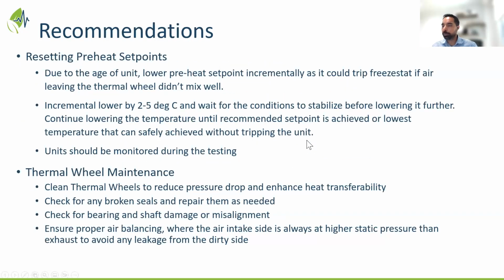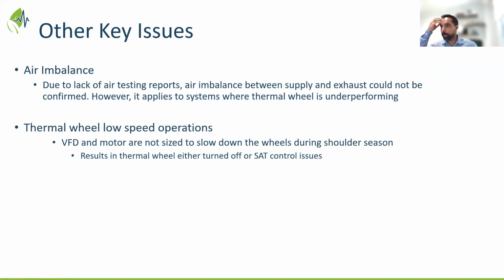A couple of other key issues: air imbalance, which needs to be documented through the air testing. We have seen in the past that the supply and exhaust airflows do not match, especially where the exhaust airflows are lower than the design or the supply. This limits the performance of the wheel, because the wheel doesn't have energy to absorb from the exhaust, which it otherwise would have if the systems were balanced or there were no leaks in the systems.